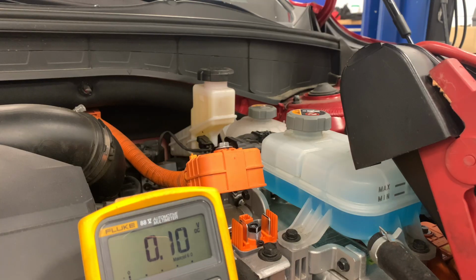Our multimeter is rated at Cat 3, so it can measure safely up to 1,000 volts, and our meter leads are also rated at Cat 3. So if your meter is rated Cat 3, but your leads aren't, you do not have a Cat 3 setup.